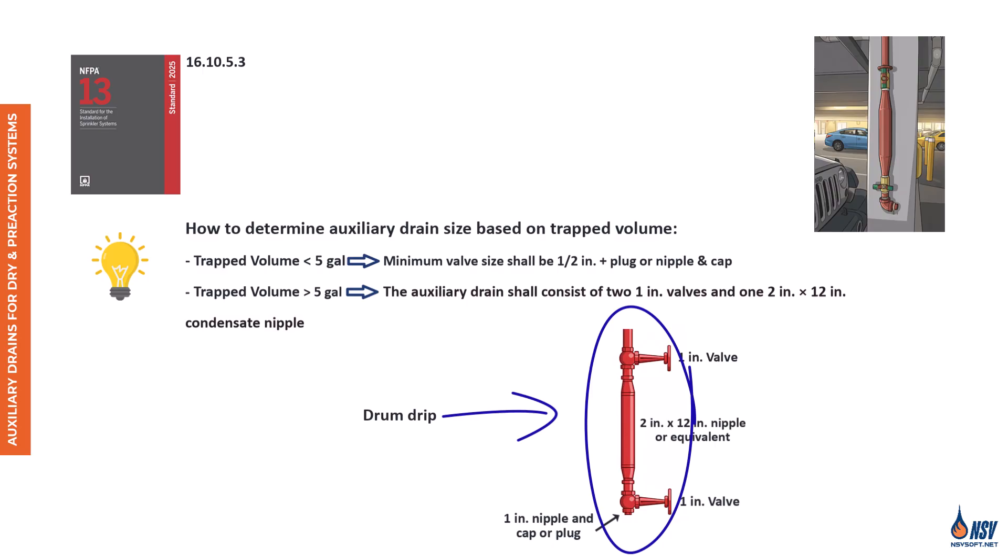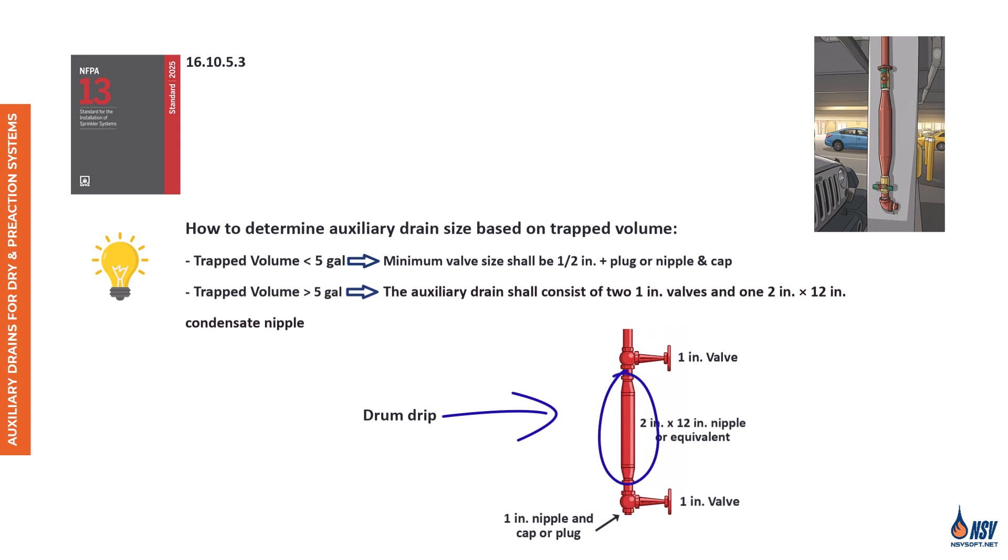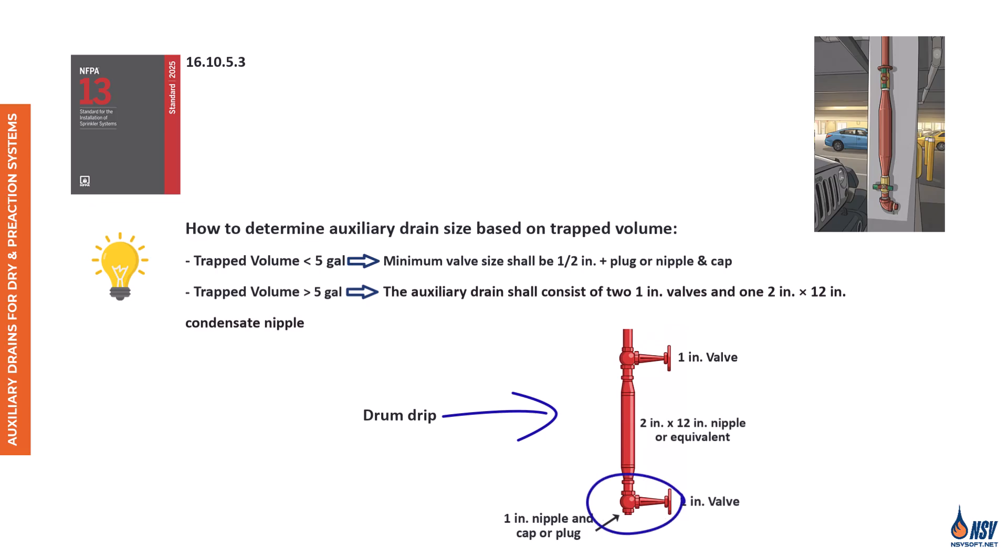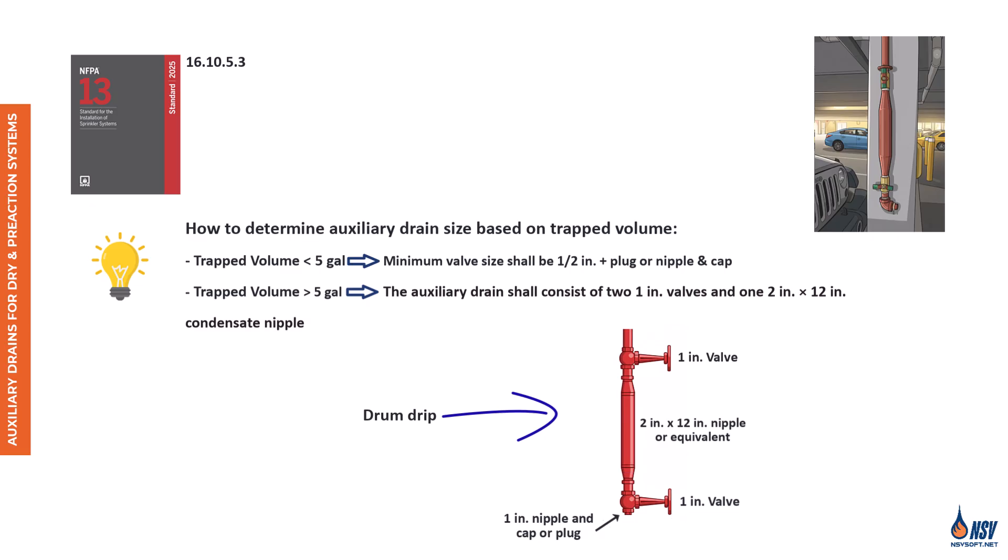The proper way to operate a drum drip is to begin with the lower valve closed and the upper valve open, as shown in the figure. Water collects in the larger diameter vertical section of pipe, which acts as a reservoir. When it's time to check the drum drip, first close the upper valve, then open the lower valve. Remove the plug and observe whether water drains out. If water does drain, wait until it completely stops. Then close the lower valve and open the upper valve. Listen for the sound of water refilling the chamber. Once you hear it, close the upper valve and reopen the lower valve to check for more water. Repeat this process until no more water drains, ensuring the system is fully cleared of trapped condensate.